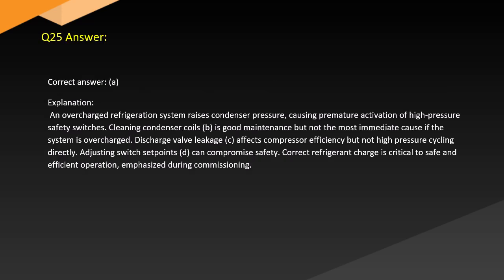Answer. Correct answer: A. Explanation. An overcharged refrigeration system raises condenser pressure, causing premature activation of high-pressure safety switches. Cleaning condenser coils (B) is good maintenance but not the most immediate cause if the system is overcharged. Discharge valve leakage (C) affects compressor efficiency but not high-pressure cycling directly. Adjusting switch setpoints (D) can compromise safety. Correct refrigerant charge is critical to safe and efficient operation, emphasized during commissioning.